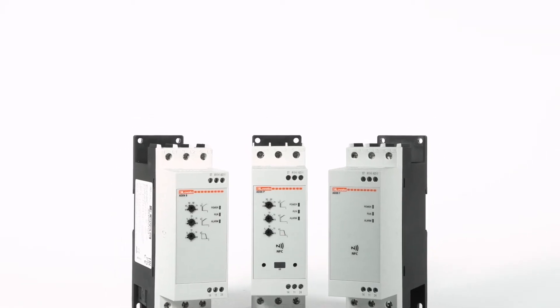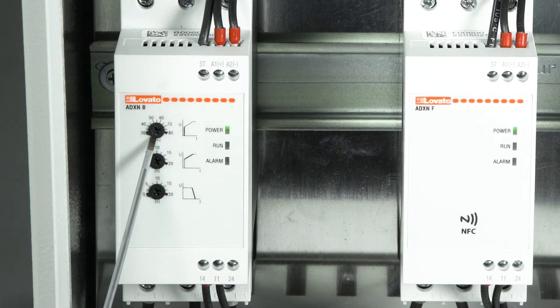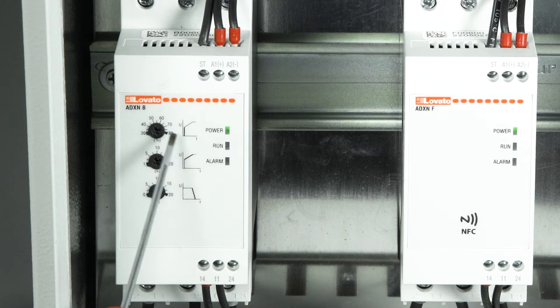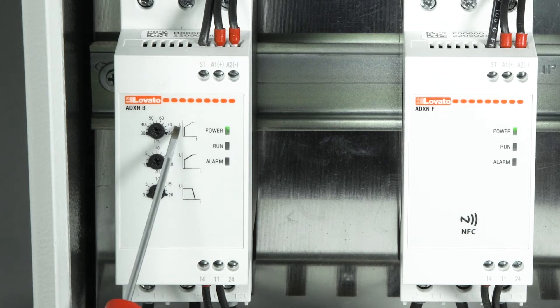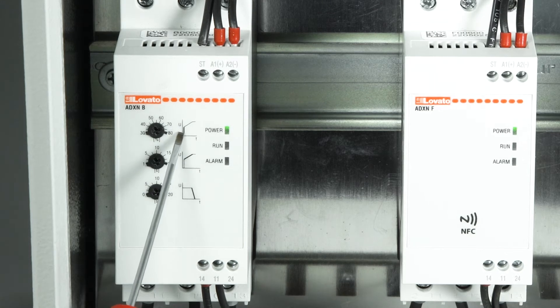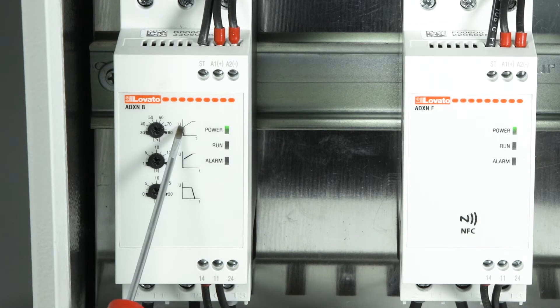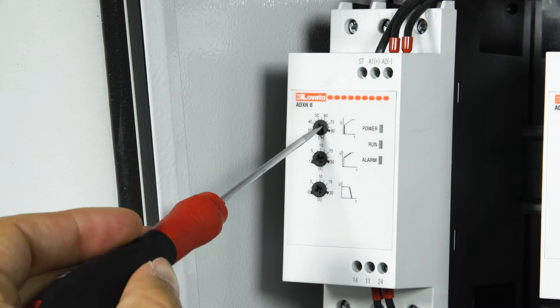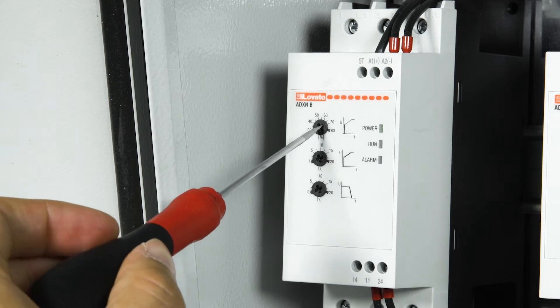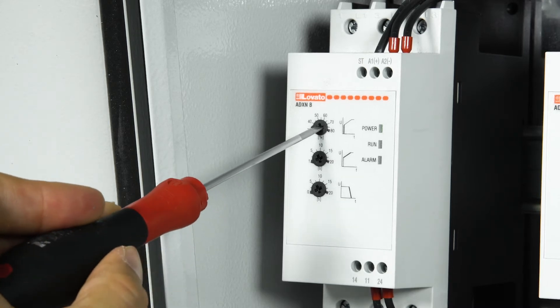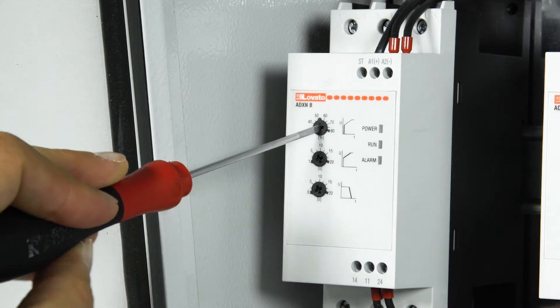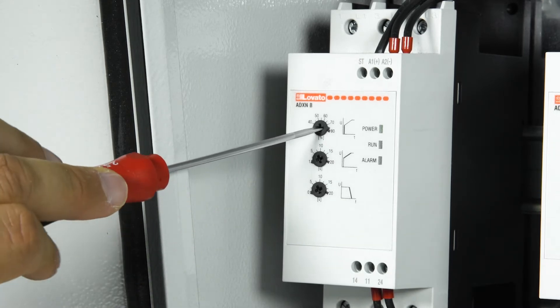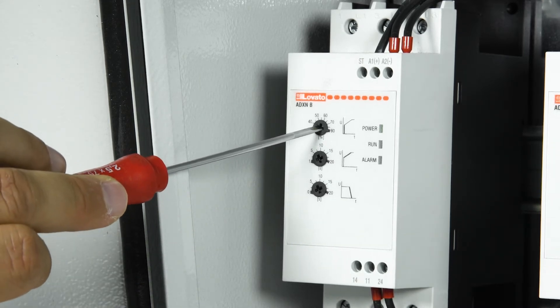With the first potentiometer, you set the starting voltage, that is the voltage step supplied by the soft starter at the start command. The step can be adjusted from 30 to 80% of the line voltage.